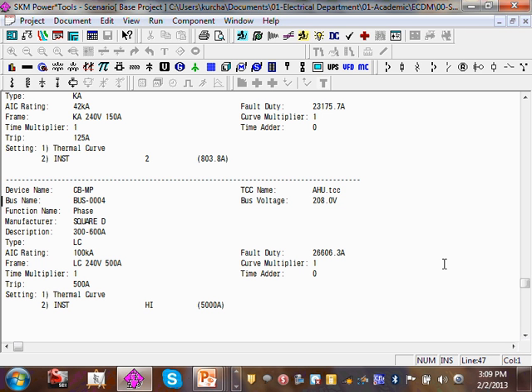Here's the circuit breaker that we're using. This is a Square D circuit breaker. It's description, 300 to 600 amps. Arc interrupting, that's the main. That's my main one. The main is rated for this amount. Here's the voltage. Here's what it's set for, 500 amp. This is the trip, 500 amp. It's thermal curve, and the instantaneous is sitting right now at the high, so it will trip at 5,000 amp.